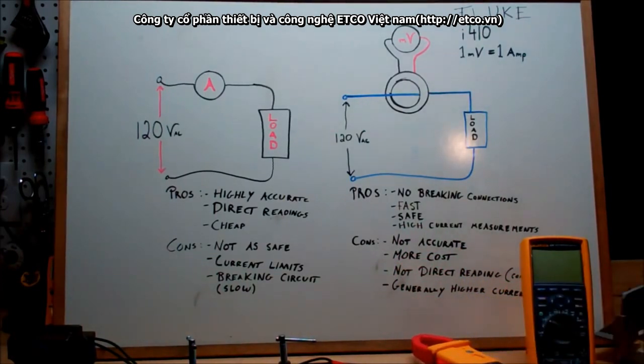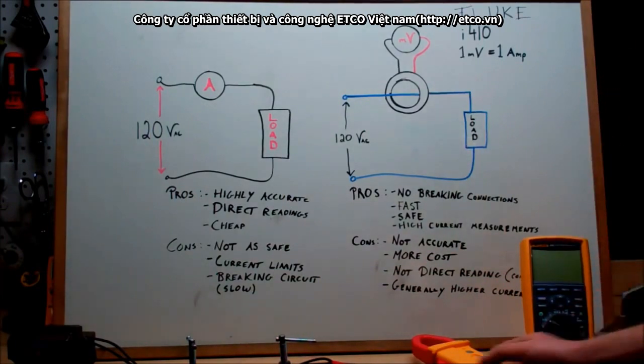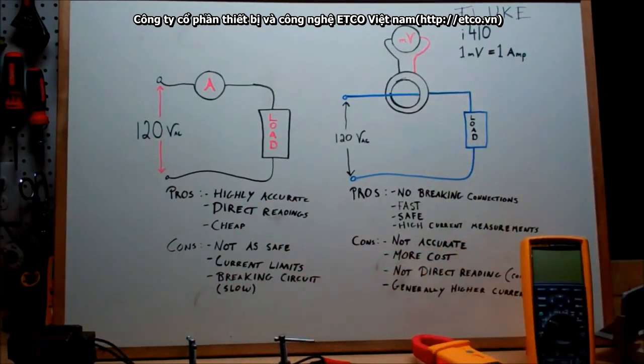Where this can measure up to 400 amps of current, and that's continuous operation. And you can get ones that hit up into the thousands. And when you're using your multimeter, it's not as safe. Like I stressed before, you start making little sketchy connections because there's a lot of exposed metal. You have to protect it from grounds. And your setup takes a lot of time. So when you're breaking the circuit, you have to look at that as a consequence.